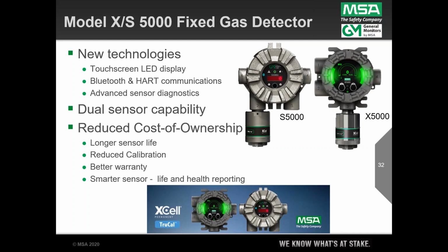On the same transmitter, and it really helps reduce the cost of ownership. The installation costs are less, and so on. And they are both touch screens. You don't need to have a magnet. They both communicate via HART as well as Bluetooth, if that's of interest. If someone's got a Bluetooth tablet, you can actually now establish comms with these transmitters and not have to be right up to them, right next to them.